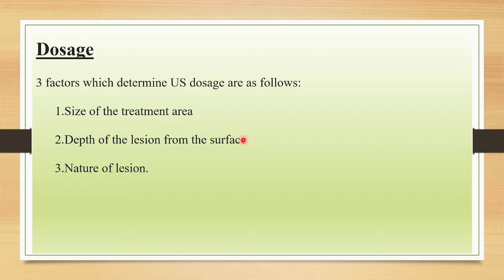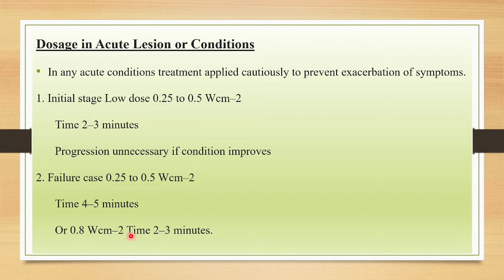In the initial stage, we will be using a low dosage, that is 0.25 to 0.5 watts per centimeter square, for 2 to 3 minutes. Progression is unnecessary if the condition improves. In failure cases, 0.25 to 0.5 watts per centimeter square for 4 to 5 minutes, or 0.8 watts per centimeter square for 2 to 3 minutes.